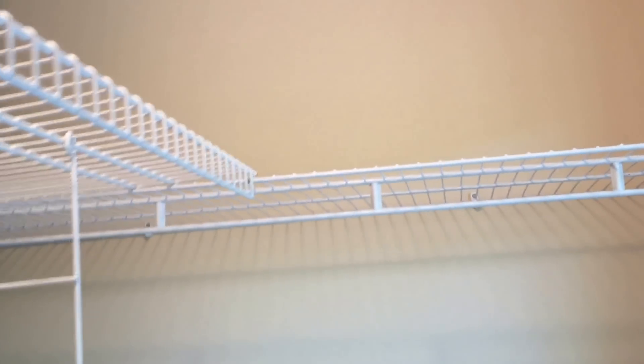In fact, it can't be within a foot of any of these shelves, which is considered storage space — and that again extends up to the ceiling. So it's a violation of section 410.16(C)(1). This is Russell Blank, NEC Consultant for EC&M Magazine.